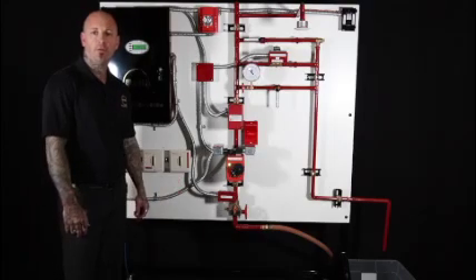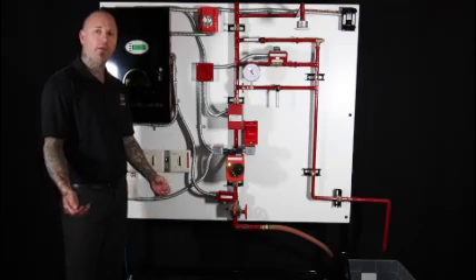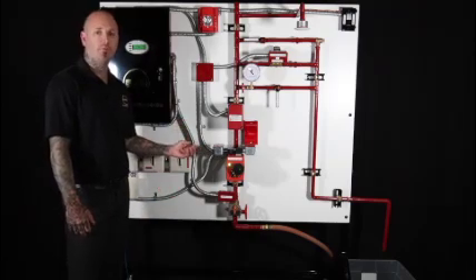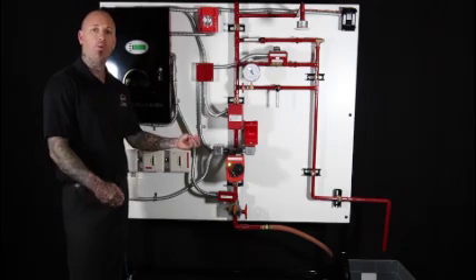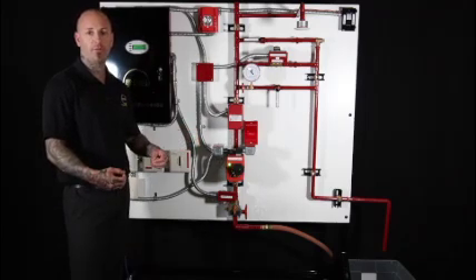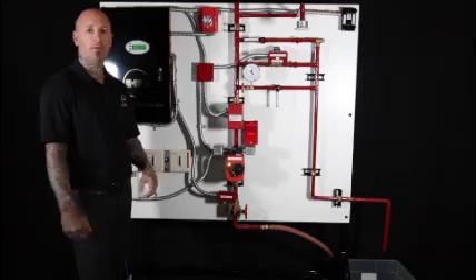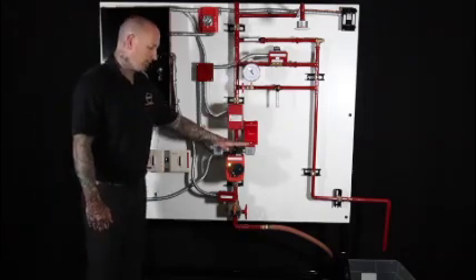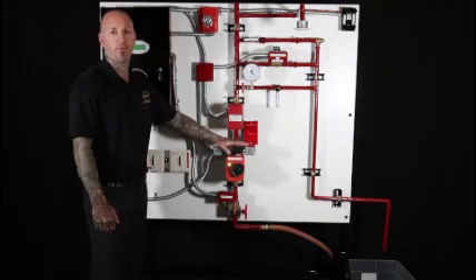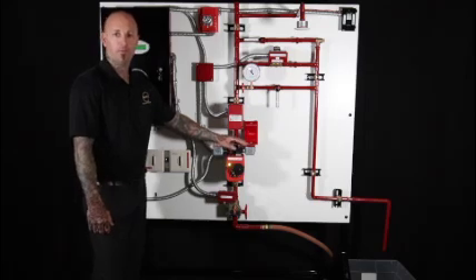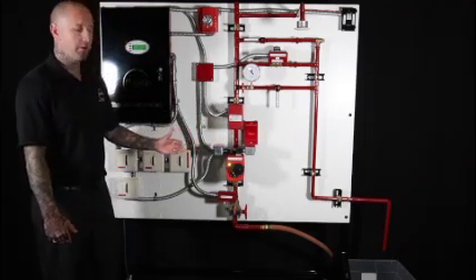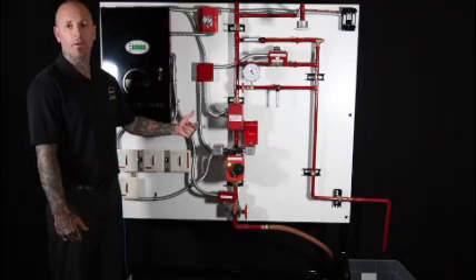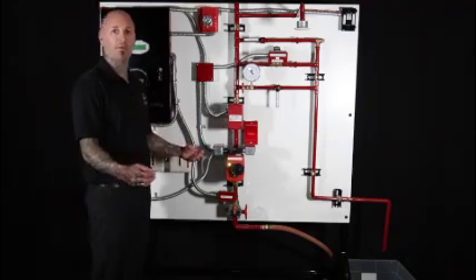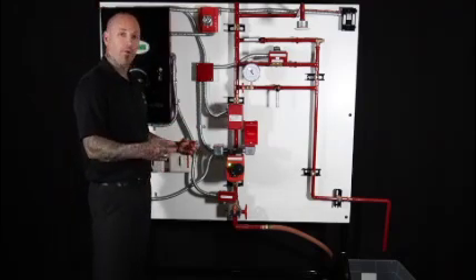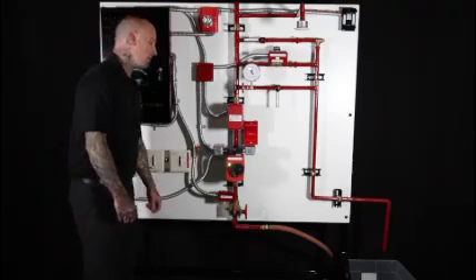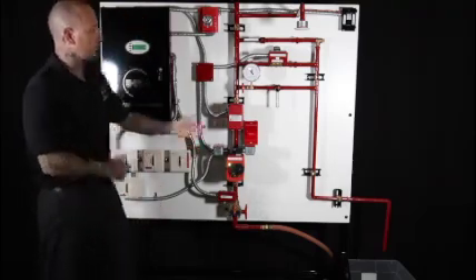Here in scenario 4, I'd like to demonstrate what would happen if we shut the water off due to a broken sprinkler pipe, but then we lost power to the system or the building. The actuator valve is designed with a battery fail-safe normally open position. So when it detects a loss of power, it will turn everything back on, creating a live system indefinitely until the power gets restored. Here's how that works.